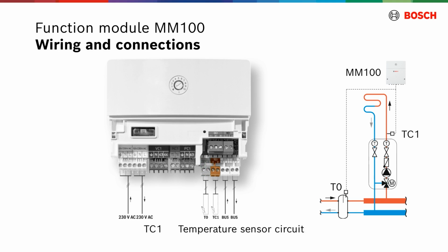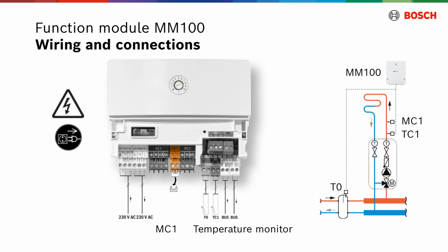Temperature sensor TC1 records flow temperature in the assigned heating circuit or the temperature of the domestic hot water cylinder. Terminal MC1 controls a temperature monitor in the assigned heating circuit. If there is no temperature monitor in the assigned heating circuit available, the bridge on the terminal must be installed. If the terminal MC1 is open, the system failure appears and the status indicator starts flashing red. Be careful as the bridge is installed on the high voltage side. The jumper for the connection MC1 is included in the set of delivery.